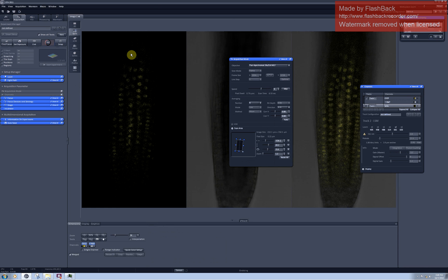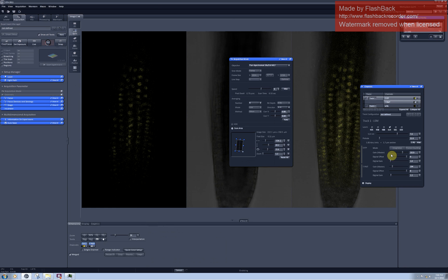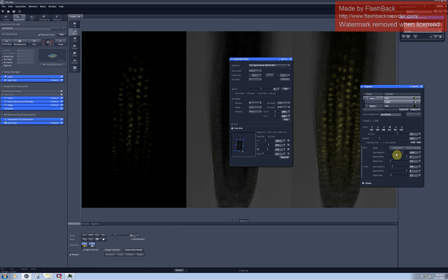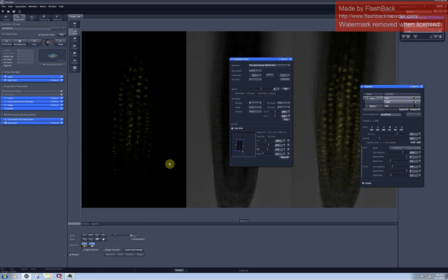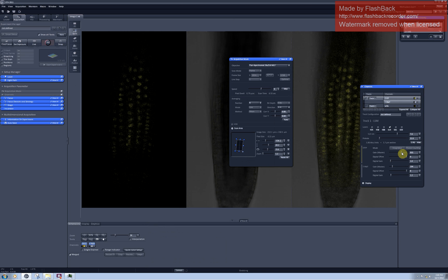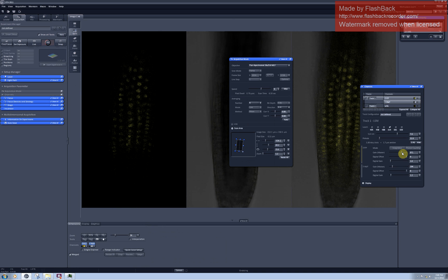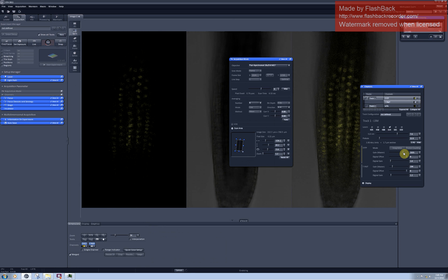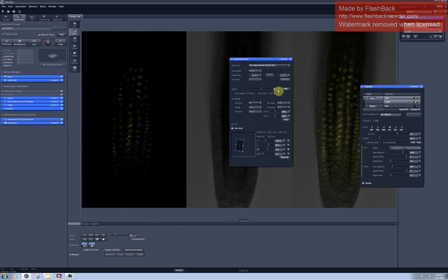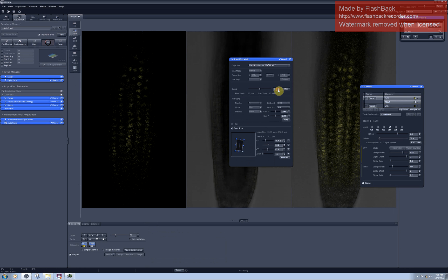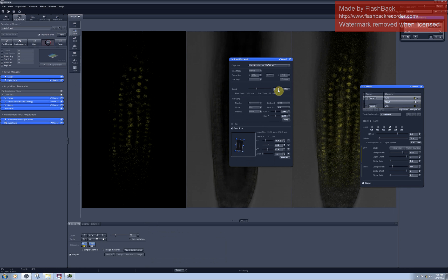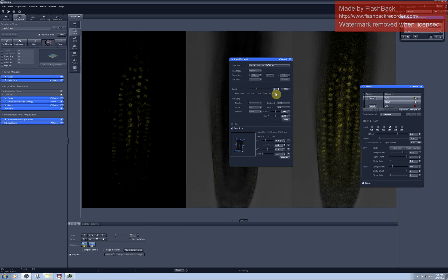The yellow fluorescence is much dimmer in this case which means that I had to pull the master gain much higher and it leads to higher noise. So what I can do I can maybe pull a bit down the master gain. Nope I can't. But I can slow down the scanning speed to get rid of some of the noise and get a decent quality.